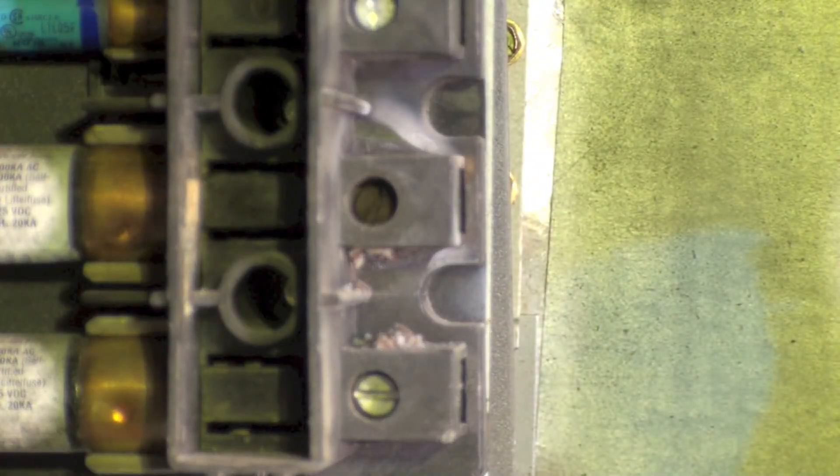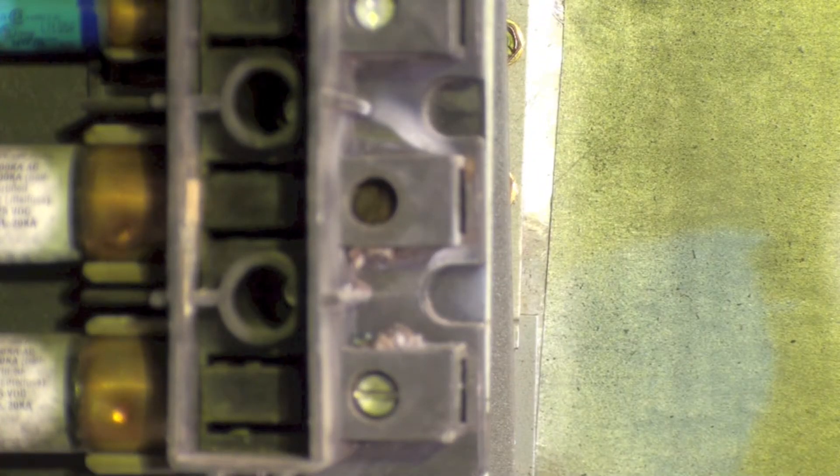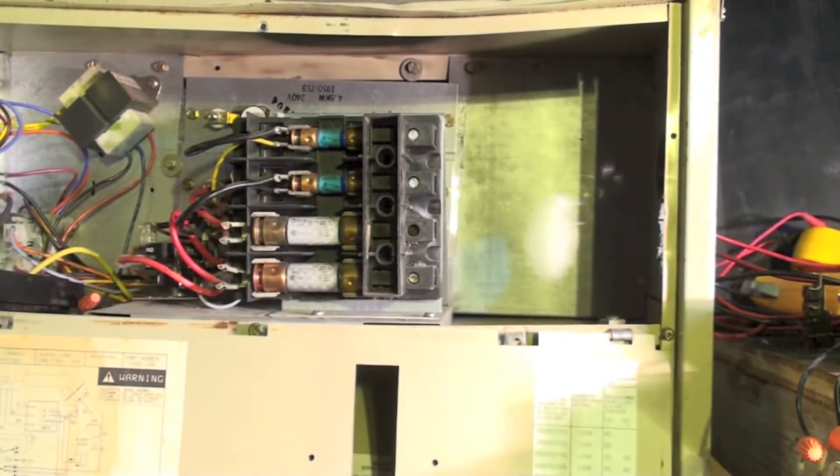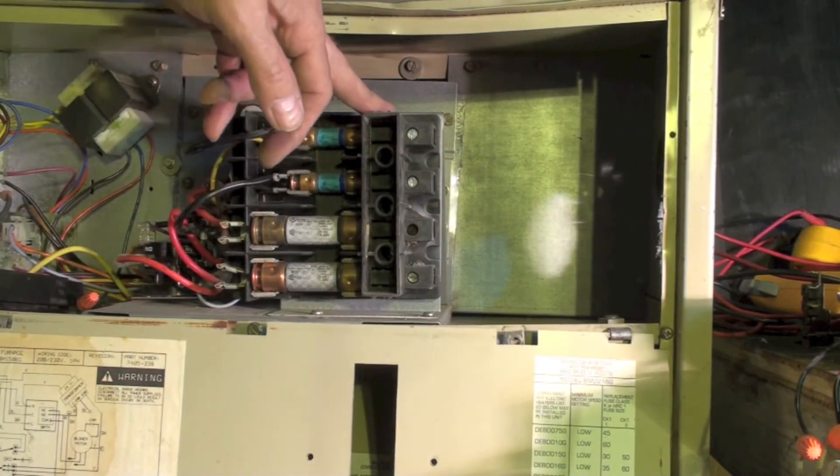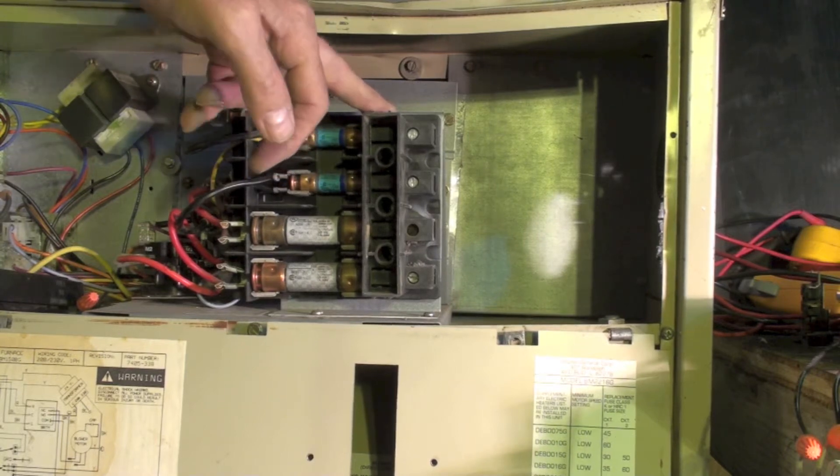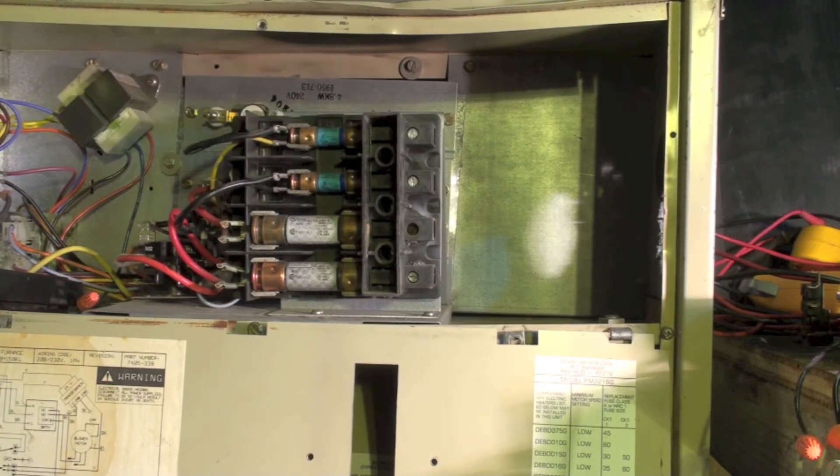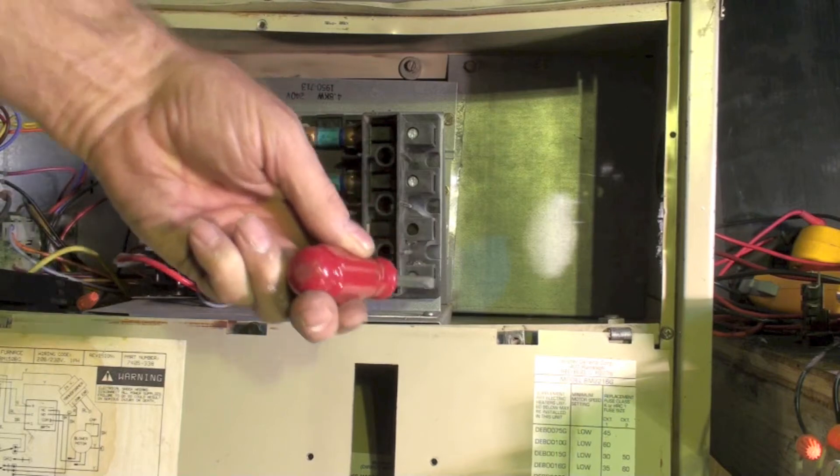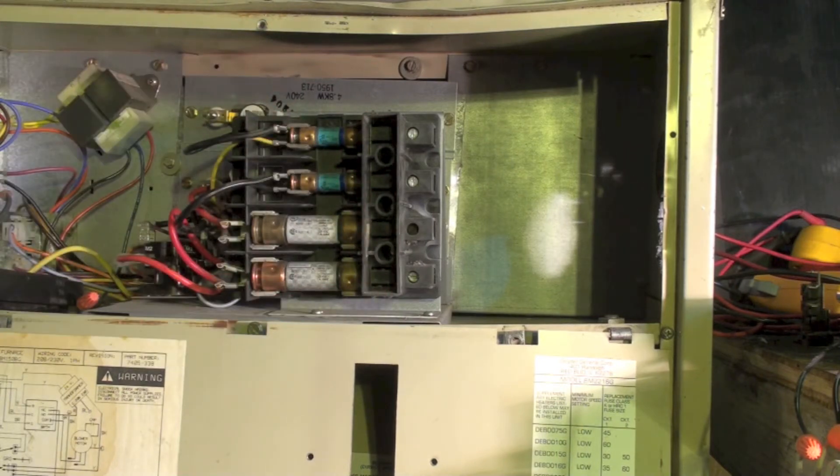Bad connection, that's all it is. These things, every year when you service an electric furnace, everything that can be tightened should be tightened. Each one of these screws should be taken down a little bit.